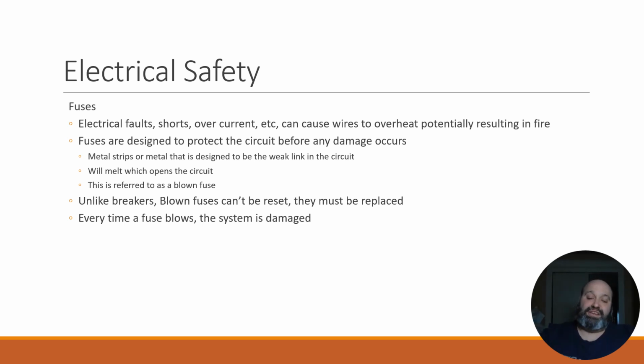So the system is being damaged, which again is why if you replace a transformer on an older system that maybe doesn't have a circuit board with a fuse that's already in it, I usually recommend putting a fused link on that low voltage side, because you'll save the system from having to replace the transformer again.